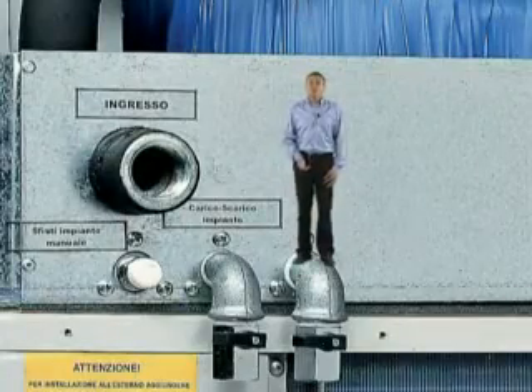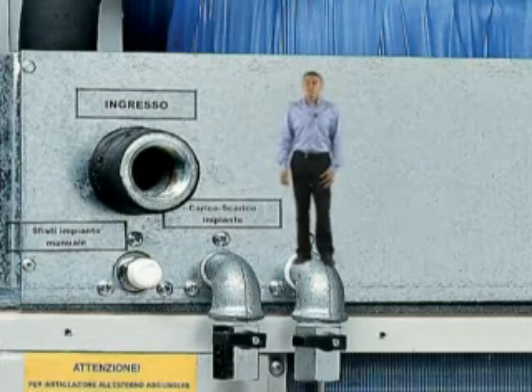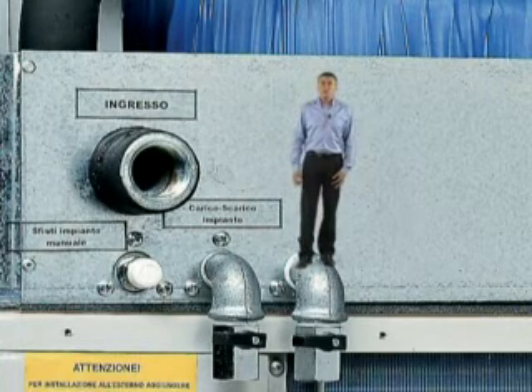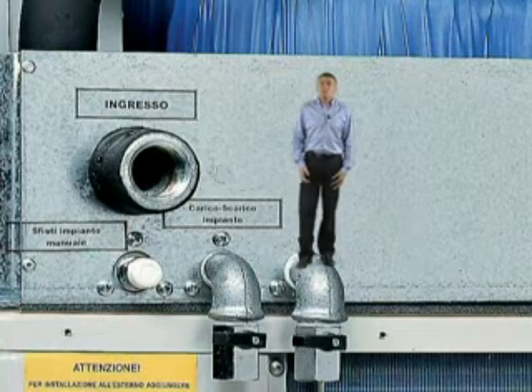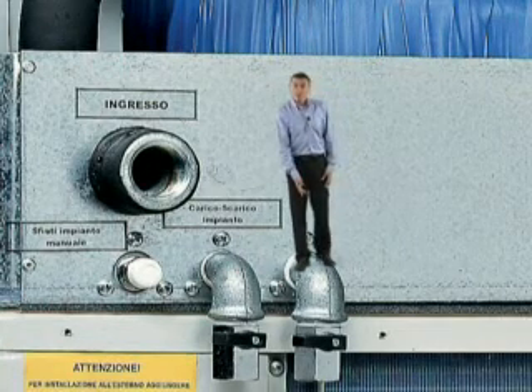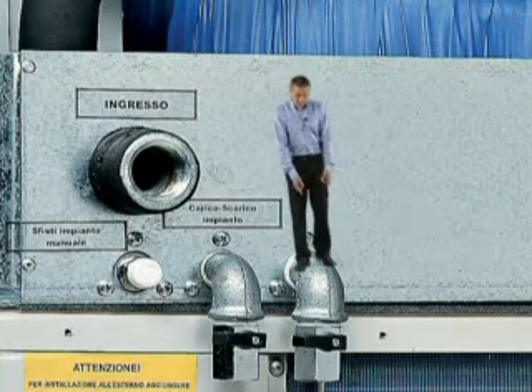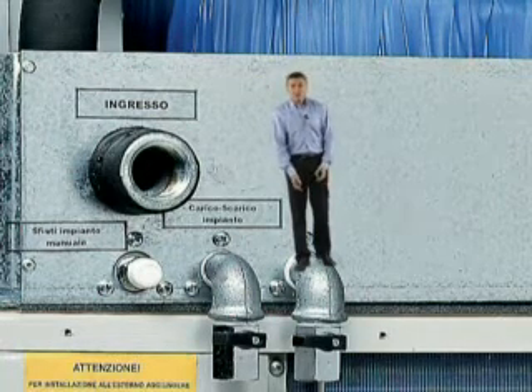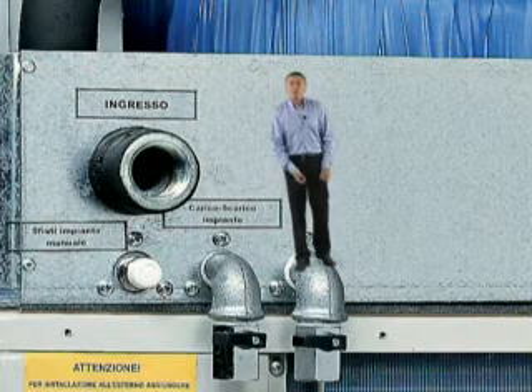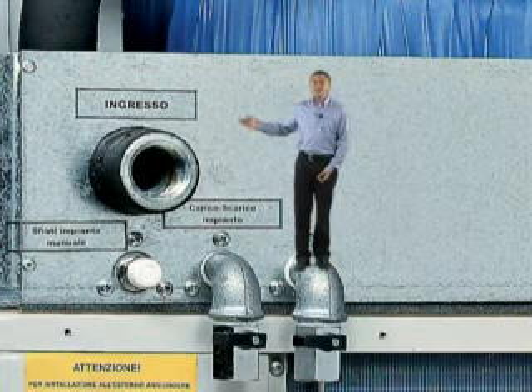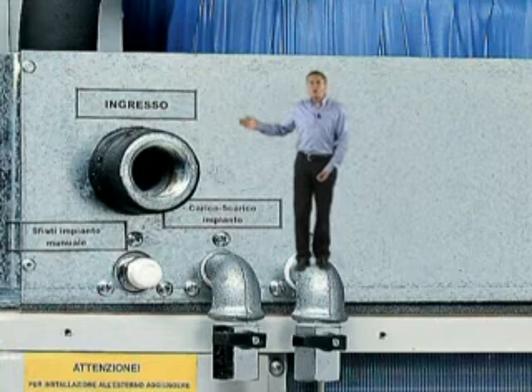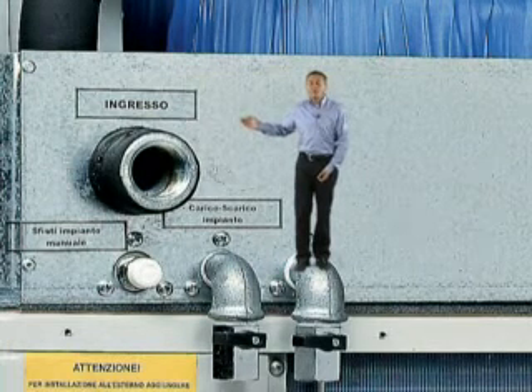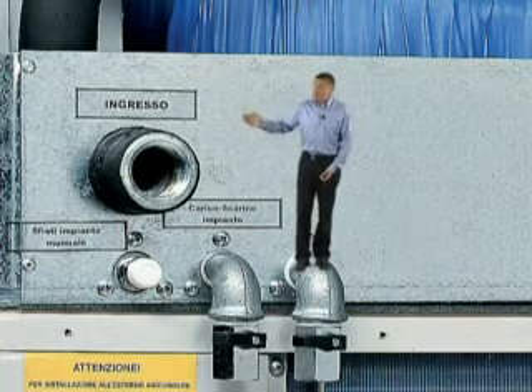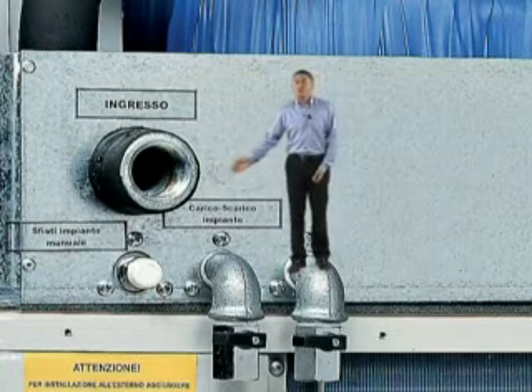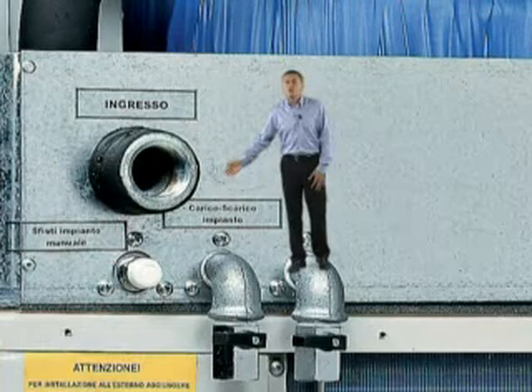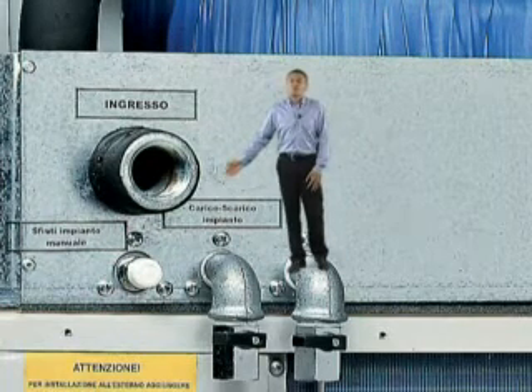We now find ourselves outside at the back to see the pipe connections. Here beneath me we can see two pipes, the inlet and outlet of the Climabox system plant. On my right you can see the water connector that allows a good operation of the fan coils in the machine entrance. And below, beneath the pipe connector joint, we find a manual bleed that allows the discharge of eventual air inside the machine.